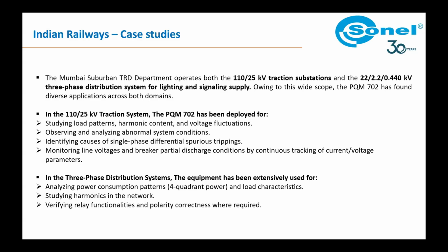Yes, it was useful. In the Sonel PQM, we can connect this equipment in a single phase with neutral measurement method, so we can monitor both phase and neutral current at the same time. In a particular case, we had differential tripping in our transformer, basically due to some bad connections on our secondary side, which we couldn't identify in the long control cable.